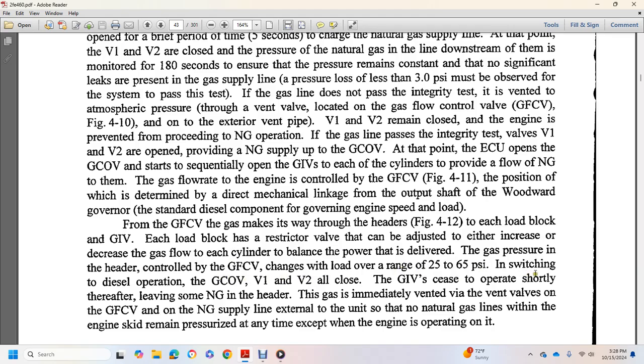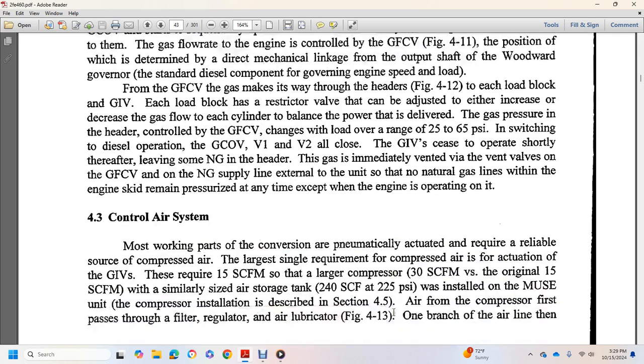The gas inlet valves cease to operate shortly after, leaving natural gas in the header. The gas is immediately vented through the vent valves, and the gas control valve and natural gas supply are isolated from the unit. No natural gas lines within the engine skid remain pressurized at any time when the engine is not operating on gas.